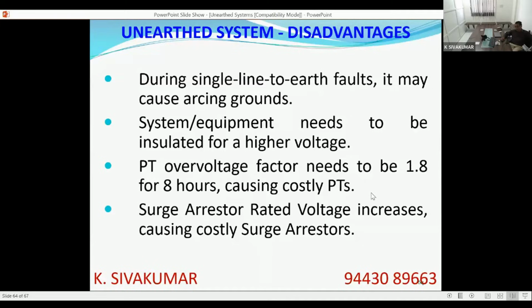Similarly, when you see the PT standard, the potential transformer standard, the overvoltage factor is very low for grounded systems. For a solidly earthed system, it is 1.2 continuous and 1.5 for 30 seconds. For the unearthed system, it is 1.2 continuous and 1.8 for 8 hours. If you order a PT with a higher overvoltage factor, it has to withstand 1.8 times the rated voltage for 8 hours. Definitely the PT will be bulky and costly. If you want to use the PT in an unearthed system, you must go for an overvoltage factor of 1.8 for 8 hours.